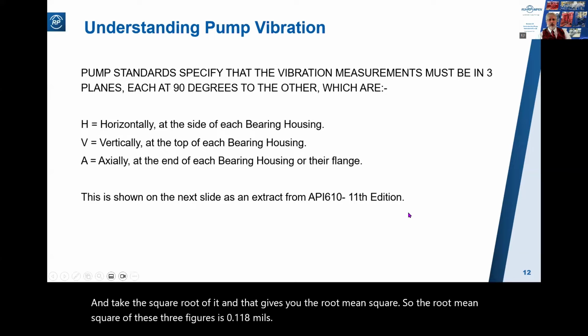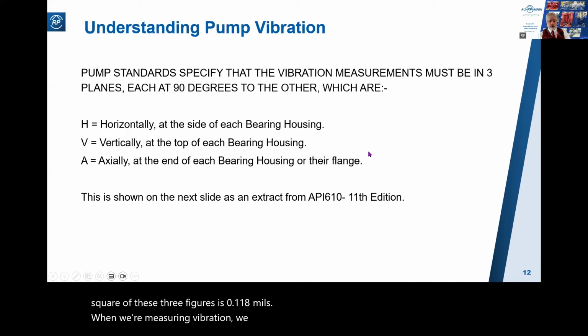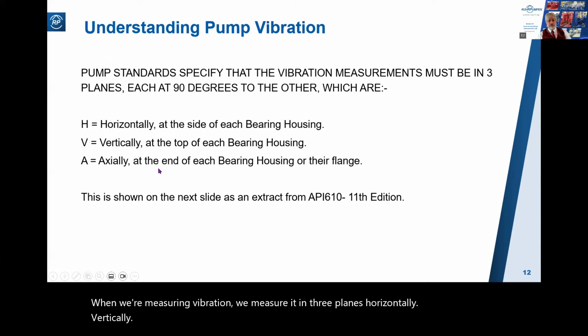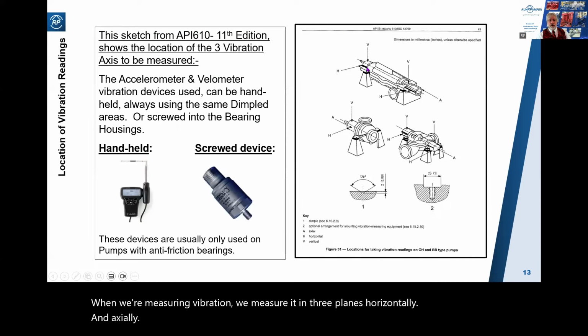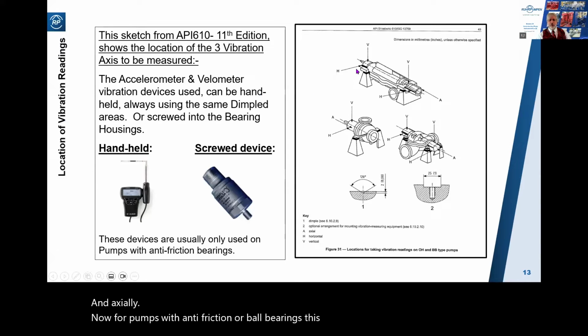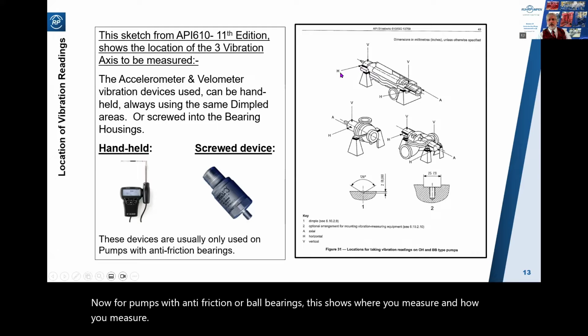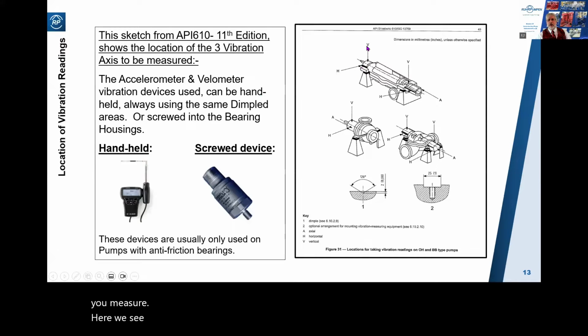When we're measuring vibration, we measure it in 3 planes: horizontally, vertically, and axially. Now, for pumps with anti-friction or ball bearings, this shows where you measure and how you measure. Here we see it: horizontal plane, vertical plane, and axial plane. There'll be a dimple on each bearing housing showing where these readings are supposed to be taken.